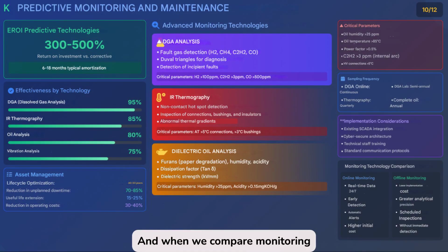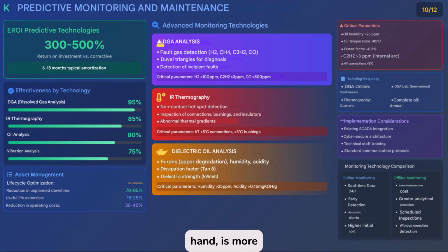And when we compare monitoring methods, we see that online monitoring has the advantage of offering real-time data, early detection, and automatic alerts, although its initial cost may be higher. Offline monitoring, on the other hand, is more economical and accurate for certain analyses, but it doesn't allow for immediate response to a critical anomaly. The choice between the two depends on the type of asset, the environment, and the company's business model, and in many cases, the optimal approach is a hybrid combination that leverages the best of both worlds: agility in detection and depth in analysis.